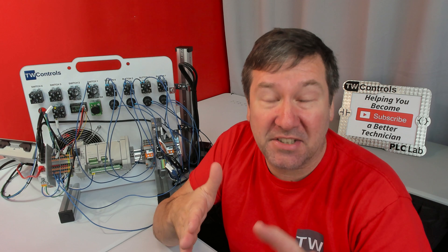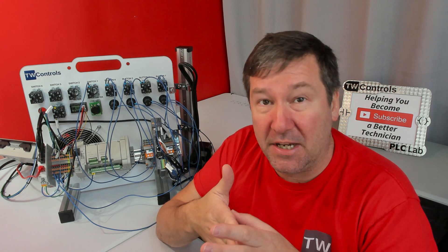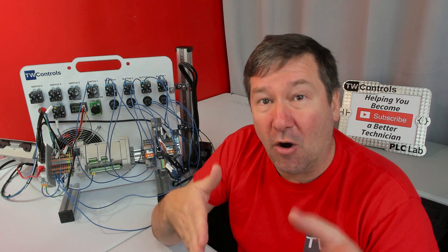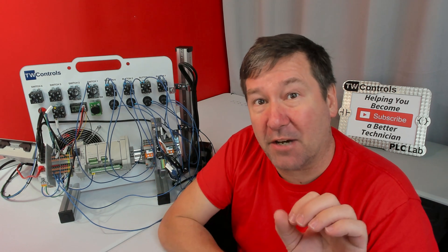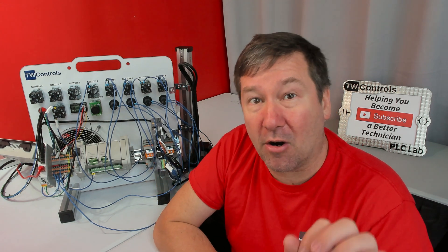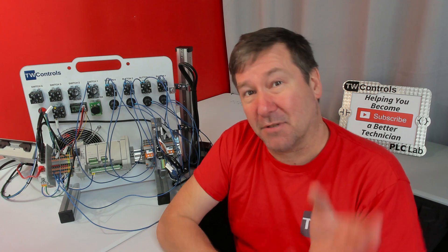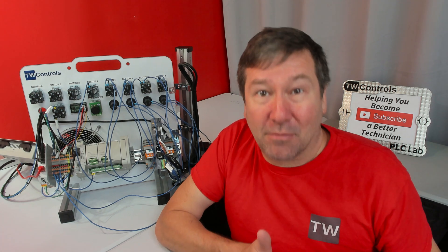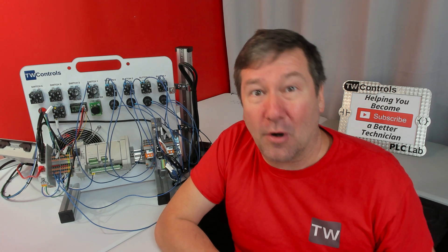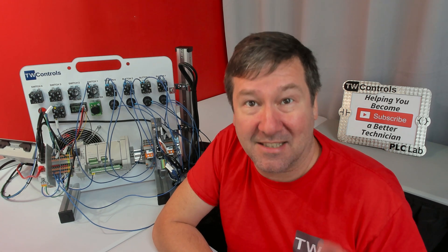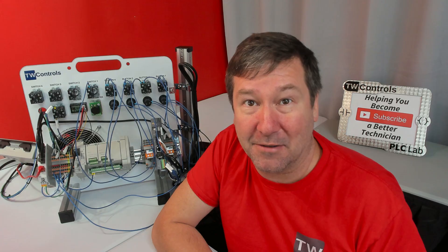Notice we skipped input 0 through 3. The first inputs on the Micro 850 are high-speed inputs, and so we're setting aside those first four so we can do some high-speed applications such as encoders.